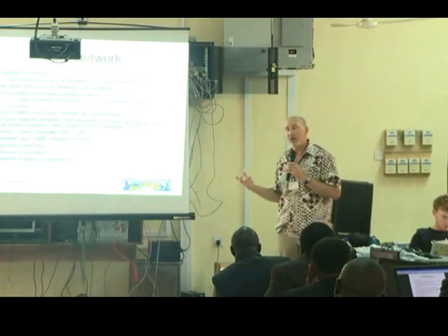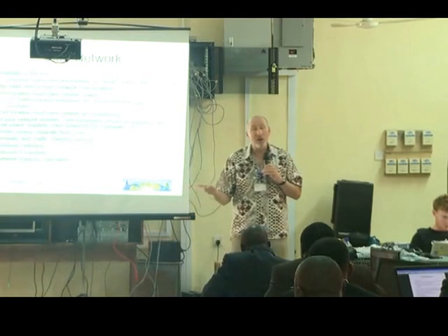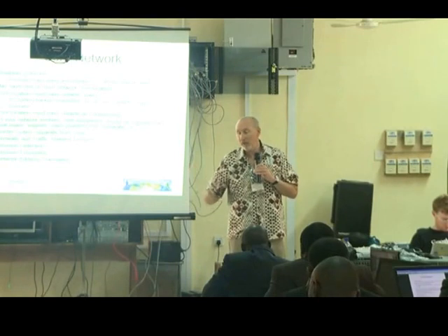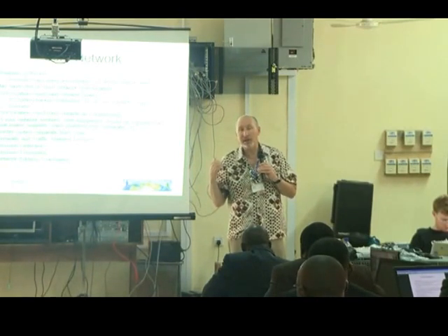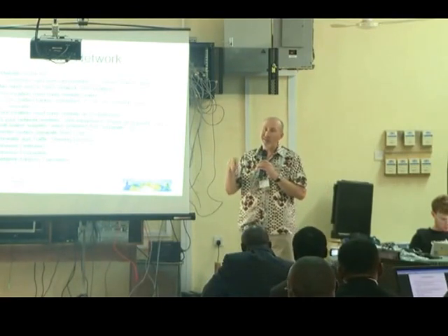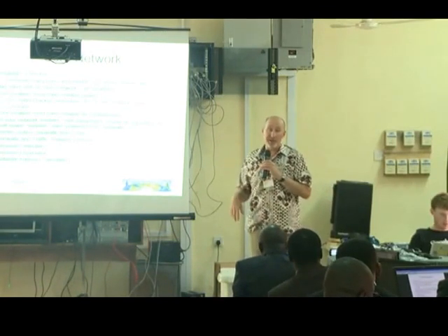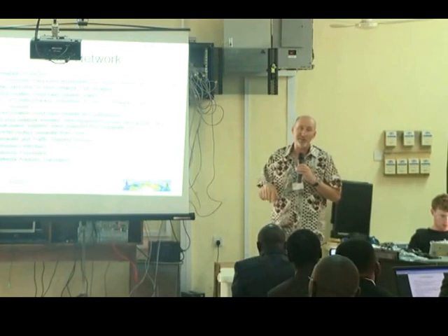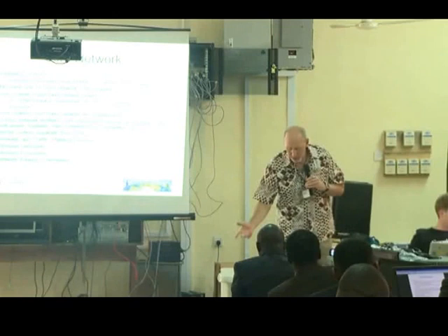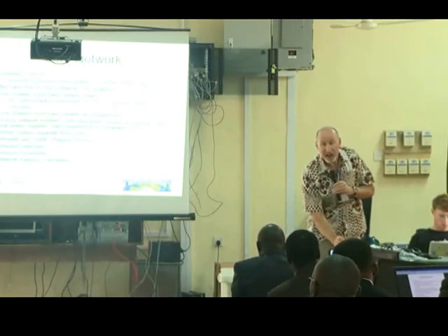But generally, on my campus, I don't provide UPSs or generator power on the switches in individual buildings. Because if the power goes out in a building, their computers are out, why do I care if the network's out? It doesn't matter. On the other hand, the core provides service to all my buildings. If it goes out, everybody's out. That's where you want to put all your investment: generation, and batteries, and air conditioning. Then you might have one or more core locations, and I actually have some examples of exactly what my network looks like.